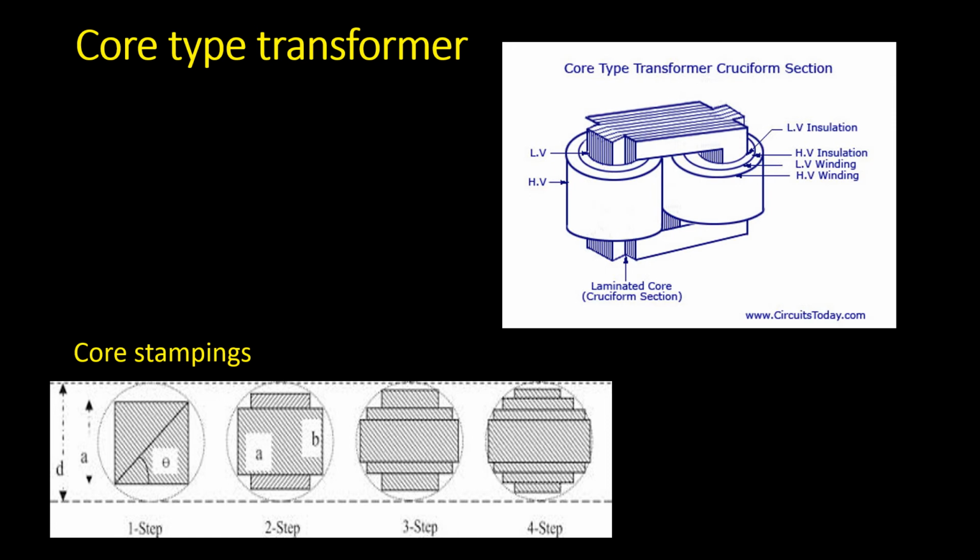Circular cylindrical coils have a fair advantage of having good mechanical strength. So instead of using rectangular coils, we are using round shaped or cylindrical type coils, and the basic reason behind it is that cylindrical type coils have more mechanical strength. The cylindrical coils will have different layers and each layer will be insulated from the other with the help of material like paper, cloth, micarta, mica sheets and so on.